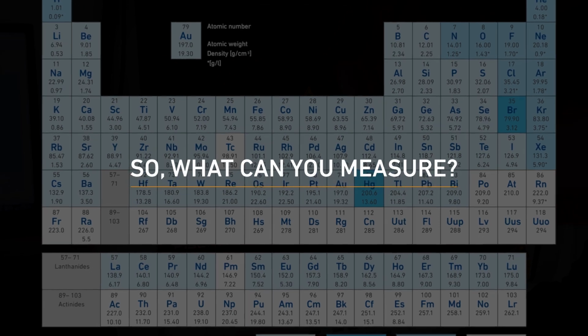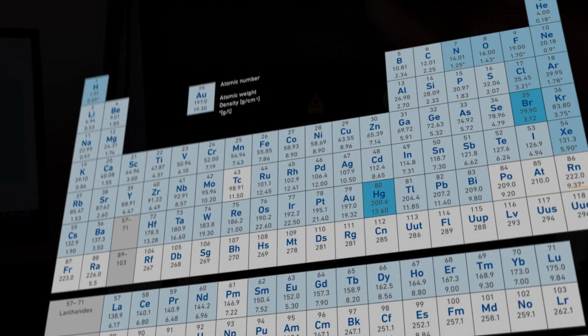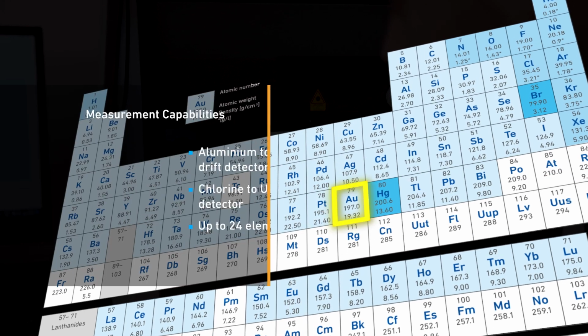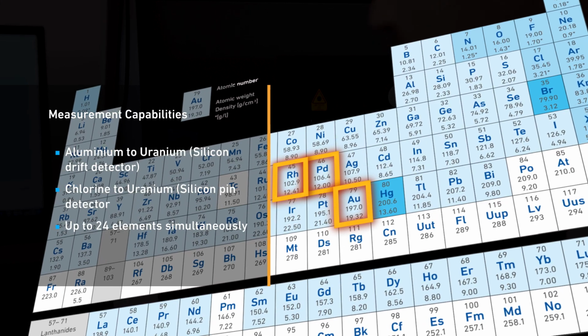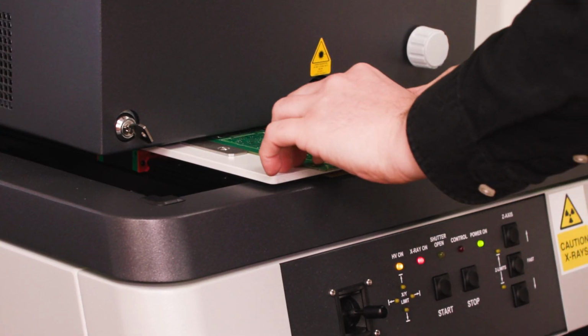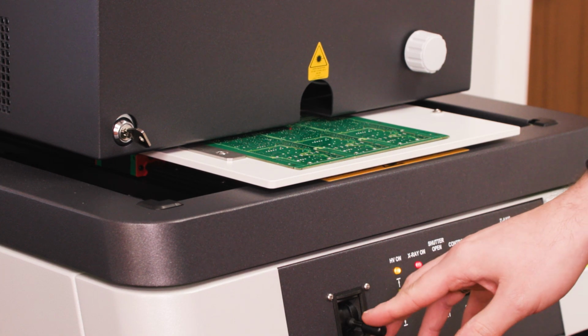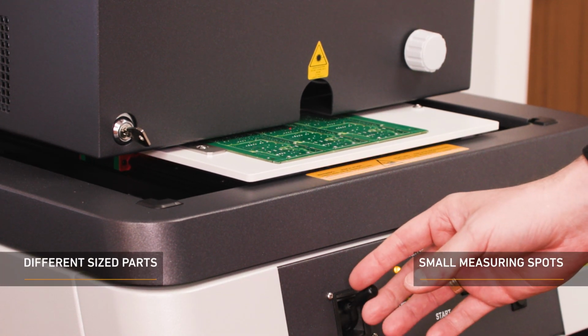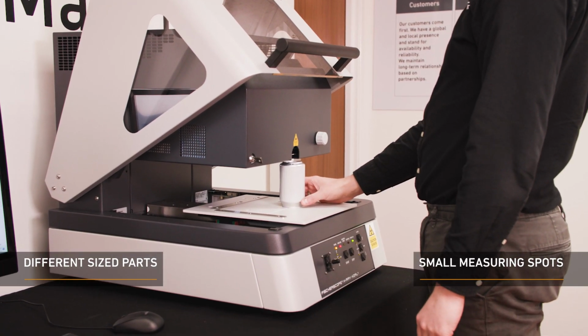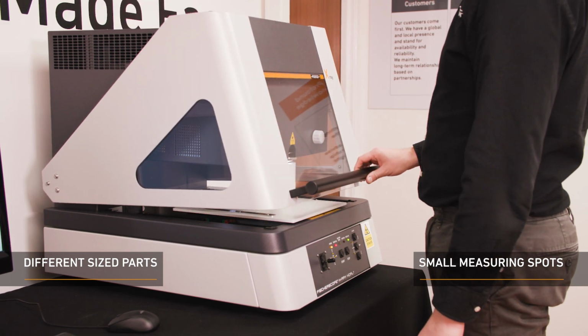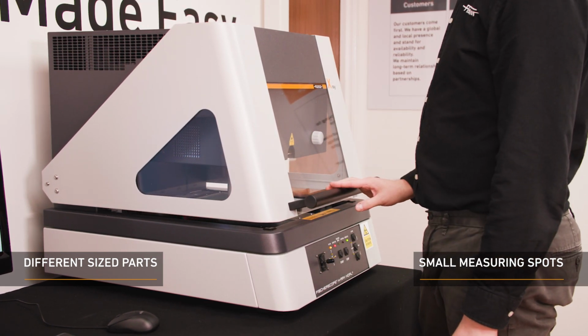So, what can you measure? You can measure a wide range of elements from aluminium to uranium, including gold, rhodium, palladium, and nickel phosphorus. With this instrument, the measuring diameter possible can be as small as 0.1 millimeters. It has a high-resolution video camera with zoom to enable easy sample positioning and precise measurement spot adjustment.